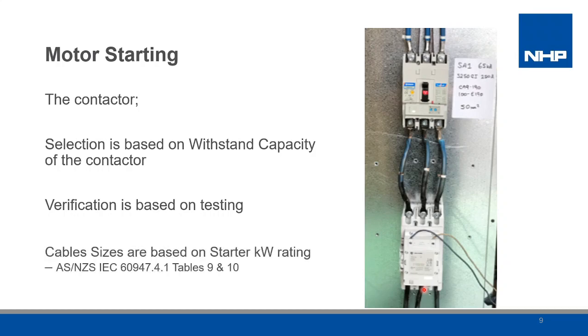Test panels are built with a maximum cable length of 2.4 meters per phase. This covers from the line connection from the test laboratory connection, interconnections and between components, and connections to the shorting link. The cables are of a cross-sectional area relative to the starter kilowatt rating.